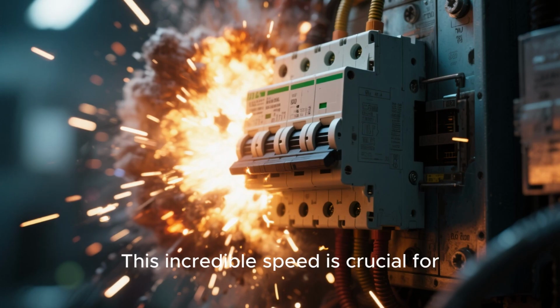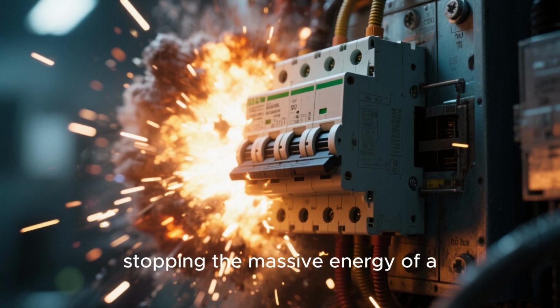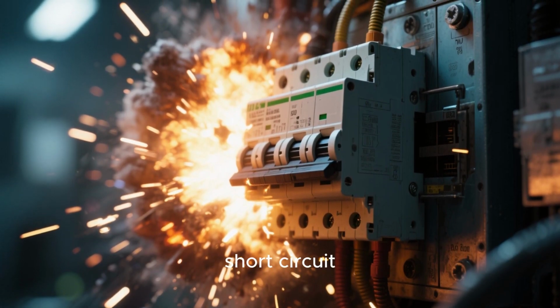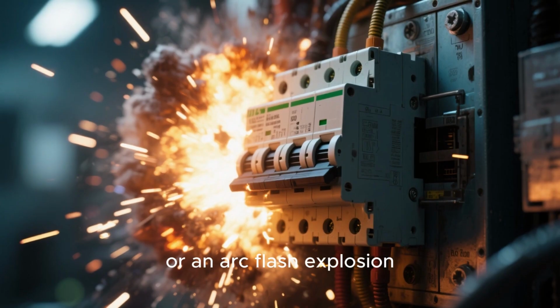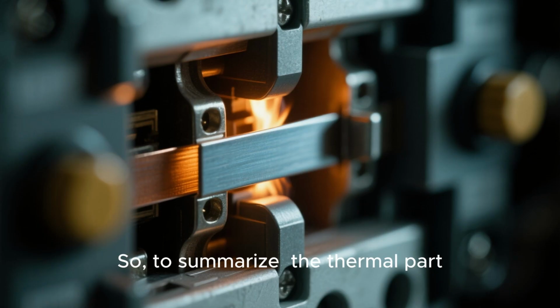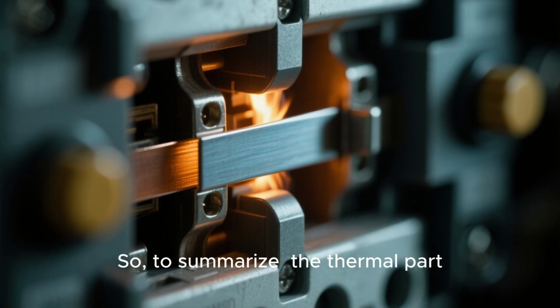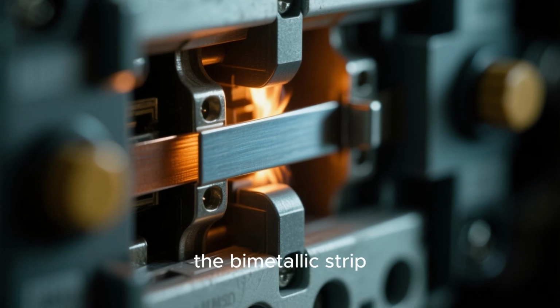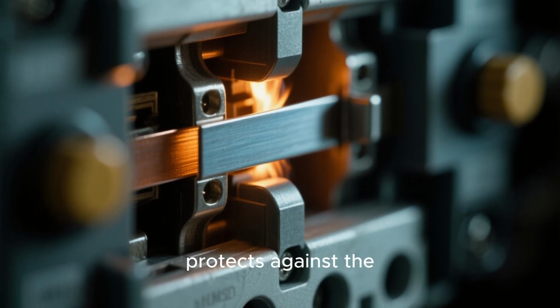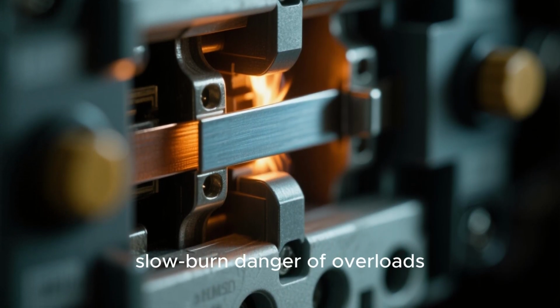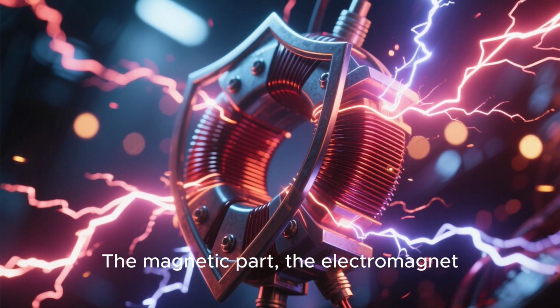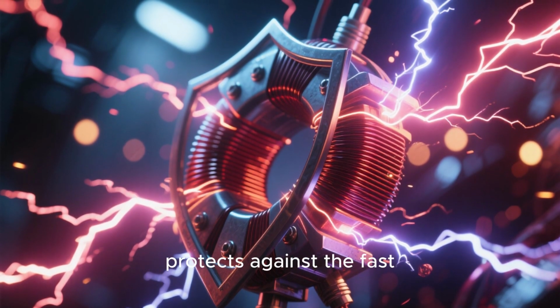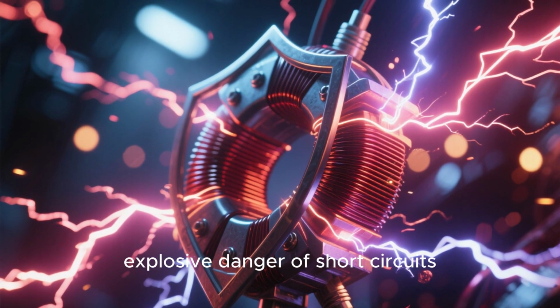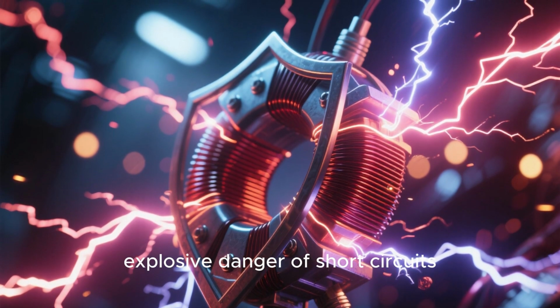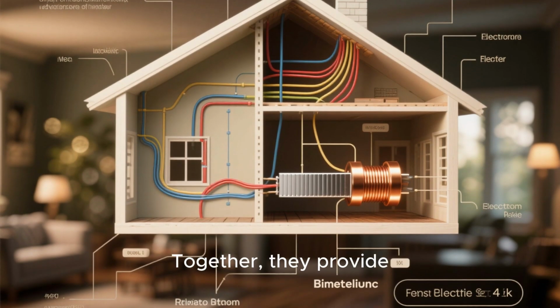This incredible speed is crucial for stopping the massive energy of a short circuit before it can cause a fire or an arc flash explosion. So, to summarize, the thermal part, the bimetallic strip, protects against the slow burn danger of overloads. The magnetic part, the electromagnet, protects against the fast, explosive danger of short circuits. Together, they provide comprehensive protection for your home's wiring.